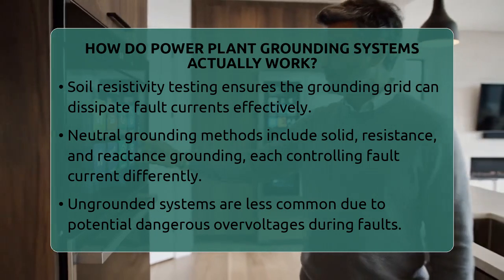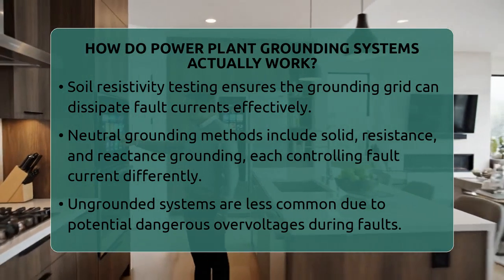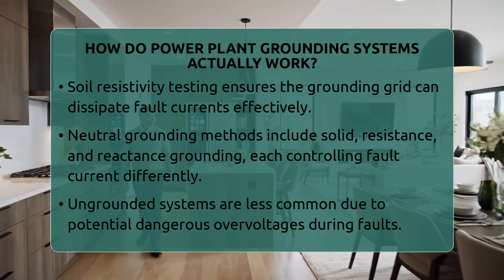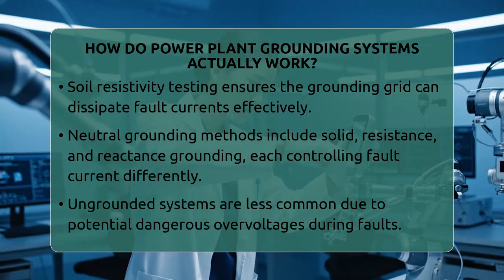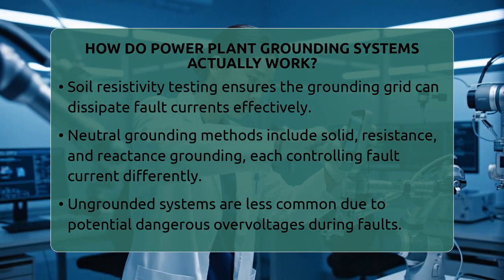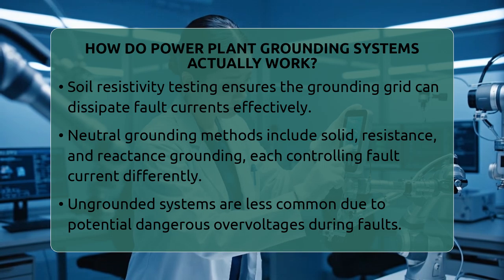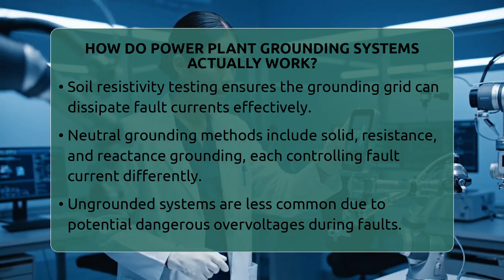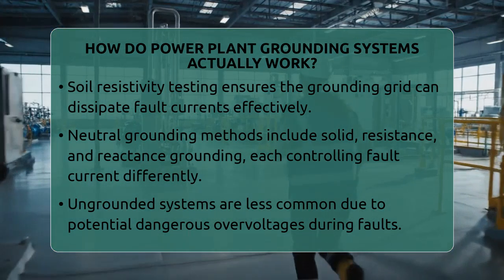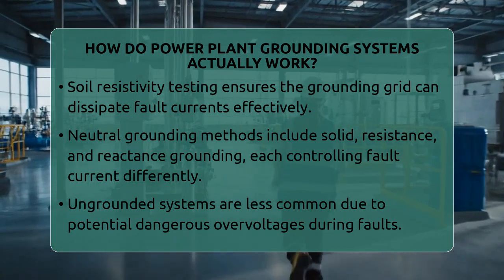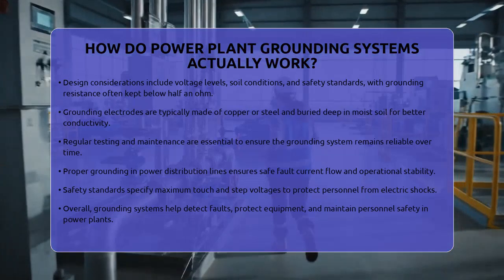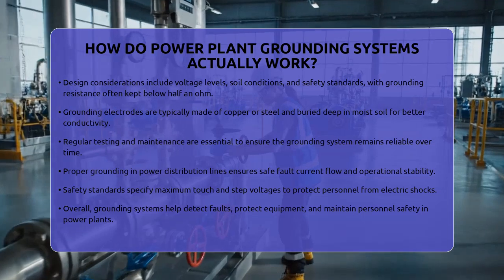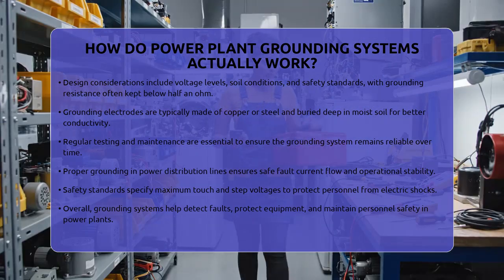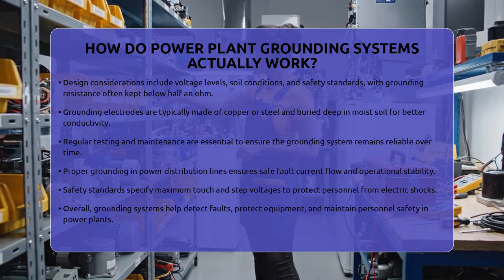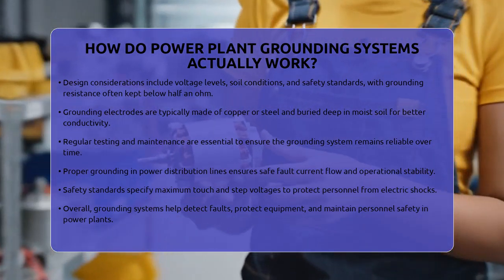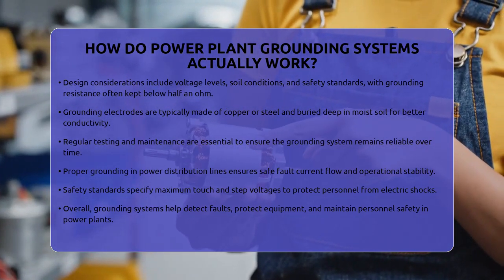For high-voltage systems over 1,000 volts, the grounding resistance must often be less than half an ohm. Grounding electrodes are usually made of copper or copper-clad steel and buried deep enough to reach moist soil, which conducts electricity better. The entire grid must be continuous and capable of handling the maximum fault current without overheating. Regular testing and maintenance, like measuring ground resistance and checking for corrosion, keep the system reliable over time.